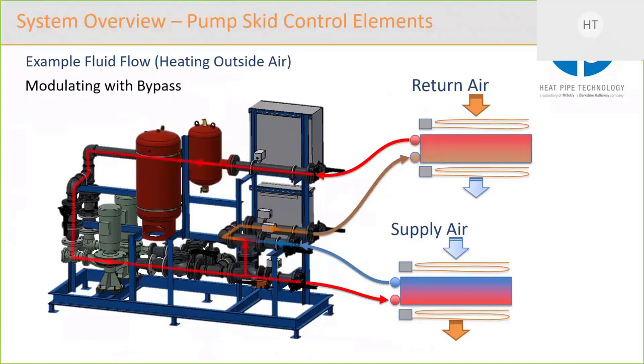So when we decide to modulate, remember I was saying that this small loop of blue water, now we've shown it as blue and orange. That's where you would want to modulate, because you're trying to hit a set point, and or because you're trying to avoid frosts on your return air coil. So you'll bypass the supply air coil a little bit to try and keep the water temperature higher.